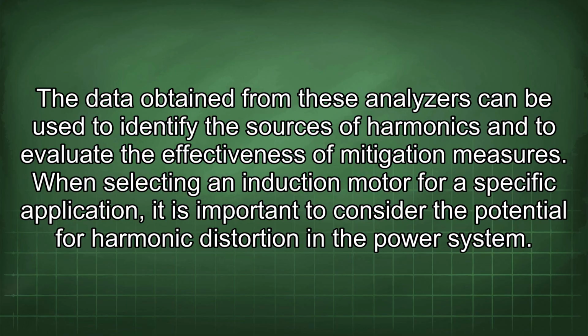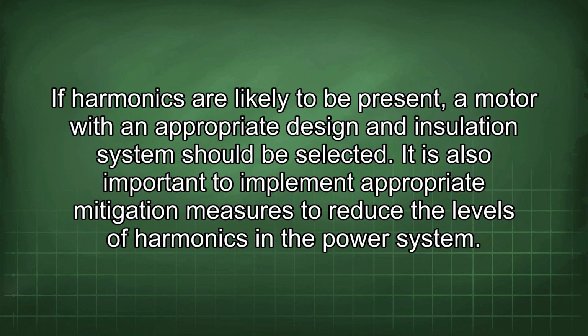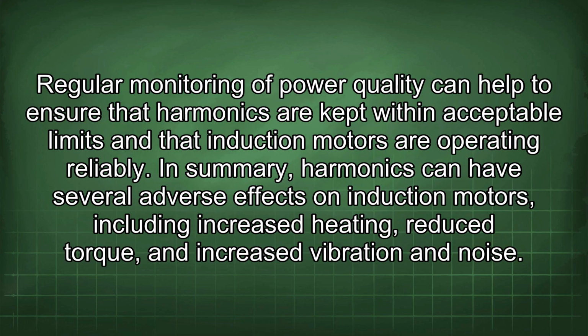When selecting an induction motor for a specific application, it is important to consider the potential for harmonic distortion in the power system. If harmonics are likely to be present, a motor with an appropriate design and insulation system should be selected. It is also important to implement appropriate mitigation measures to reduce the levels of harmonics in the power system.